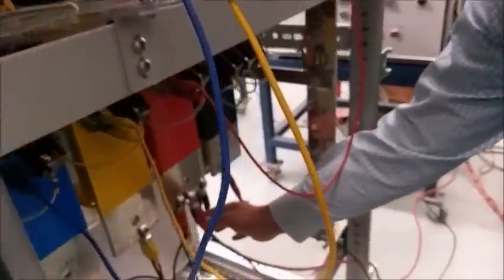So now see, here we have applied it. What we have done is shorted the RYB phases together, and we have provided one supply terminal over here, and the other is to neutral. So how is HV performing? Three phases with respect to neutral. This is the dielectric test.